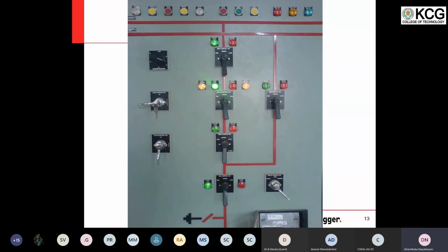25 means synchronization check. So synchronization check is a control function, not a protection function. So it's a very important area to understand in power system protection. In fact, the first lesson for a power system protection student is the ANSI codes understanding. So based on that, I have been talking like 89A, 52, 89B like this. This may be 89L and 89T like transfer isolator. Bus A isolator 89A, bus B isolator 89B. Like this it goes on. We also have some additional switches here. So this understanding is also very important.